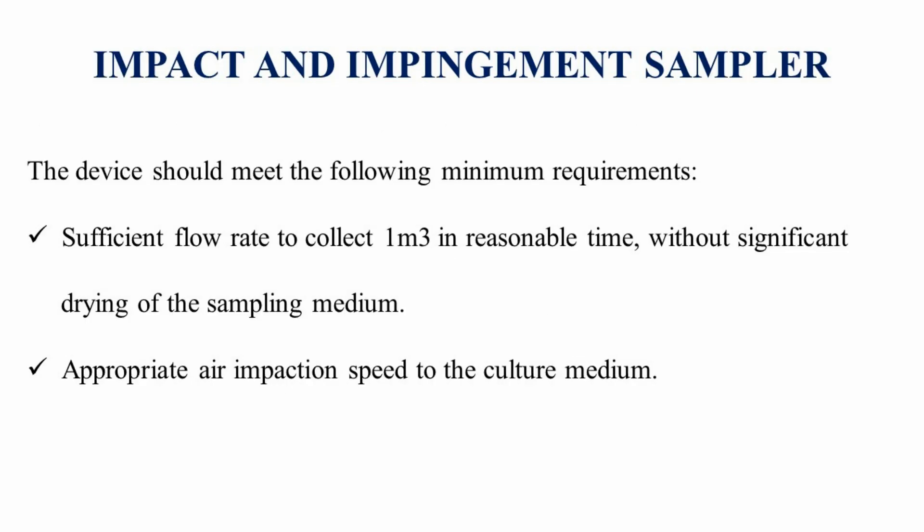Impact and impingement samplers. These devices should meet the following minimum requirements. First, a sufficient flow rate to collect one cubic meter in a reasonable time without significant drying of the sampling medium — the time required to sample one cubic meter should be nominal and during this time the media should not get dry. Second, appropriate air impaction speed to the culture medium — sampling speed should be suitable to allow collection of viable particles on the agar plate.